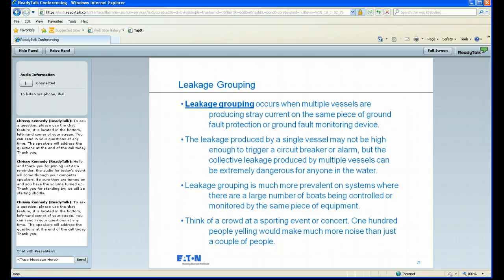Just want to give an idea of what we meant by leakage grouping a little while ago. There are probably tons of different terms used to describe this, but basically it's the collective result of multiple boats that could be producing stray current into the water. Basically we're going to get multiple vessels that are putting small amounts of current onto a system, either protected by a piece of ground fault protection or a monitoring device. Leakage produced by a single vessel may not be high enough to trigger a circuit breaker, but the collective leakage by multiple boats may cause something similar to a 30 milliamp circuit breaker or a 100 milliamp alarm to go off, depending on the amount of leakage being put into the water.